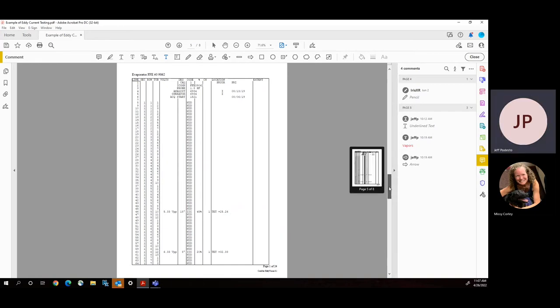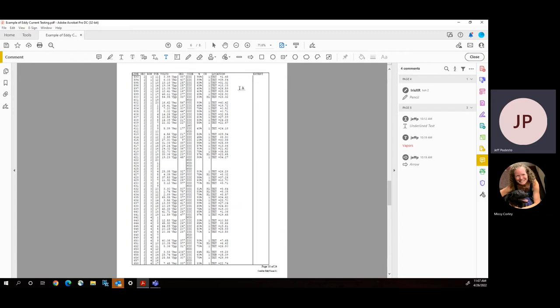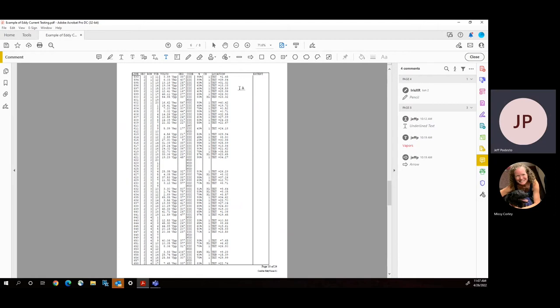When you get down to an area like this, where we've got a lot of failures in an area, and they're all in a particular area, and what's interesting about this is that we find that the depths are all over the place. Some of them are 30 feet down, some of them are only 19 feet down, some of them are 13 feet down. That's important because it tells us that we've got failures along the whole length of the tube and not in any particular depth in the tubes. This kind of leans towards us beginning to realize that maybe we've got some type of corrosion situation going on, or we've got the effects of maybe a CIP wash on the tubes. But it's important data that allows us to determine from the testing what might be going on and why the evaporator is failing.